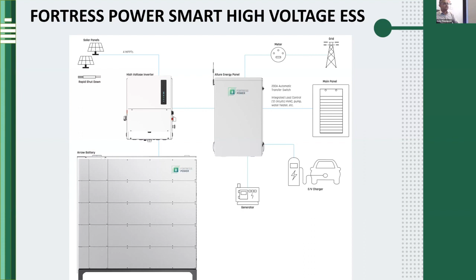Why are the high voltage inverters much cheaper? What is the difference? In the high voltage unit, it doesn't have the automatic transfer switch. It also doesn't have the rapid shutdown transmitter. All of those are built into the smart energy panel instead. So without having to build in the ATS and the rapid shutdown transmitter, the high voltage inverter is going to have a lower manufacturing cost.